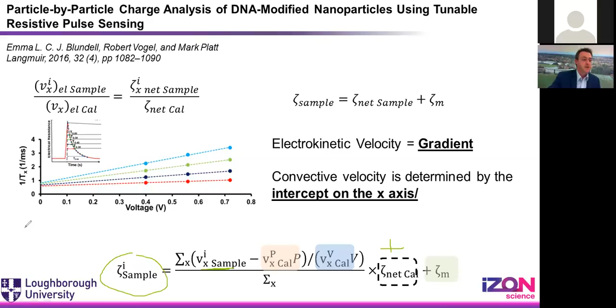So every time that we do a particle measurement, and this is the same if you take an average of all the particles or an individual particle, the zeta potential of the sample that you're looking at can be derived from measuring its velocity and a rearrangement of this calibration plot. So you take away the intercept, divided by the gradient, and times by the calibration zeta potential. And then you can account for the changes in the system as you go through and make the measurements of your sample. So this is as close to the technique and mechanism that IZON will, if you like, send out when they guide you through a zeta potential measurement. This is, if you like, the equation which is being crunched in those spreadsheets.